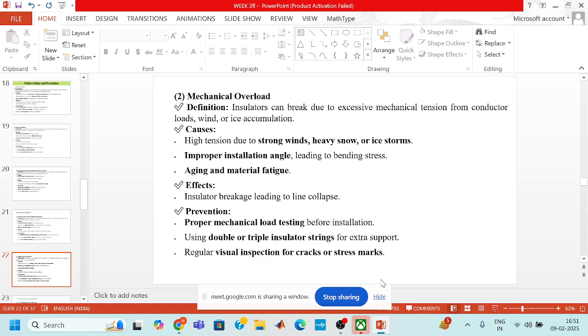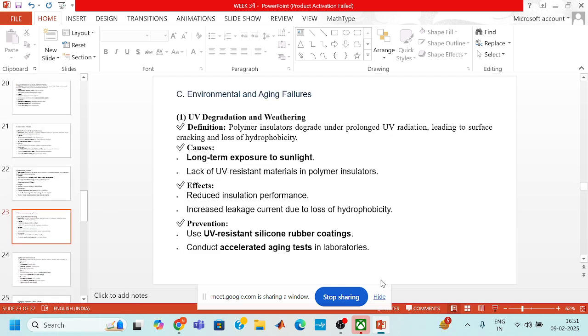leading to line collapse. So we must do proper mechanical load testing before installation, and we can also use double or triple insulator strings for extra support, and regular visual inspection for cracks or any stress marks. So C part is environmental and aging failures.